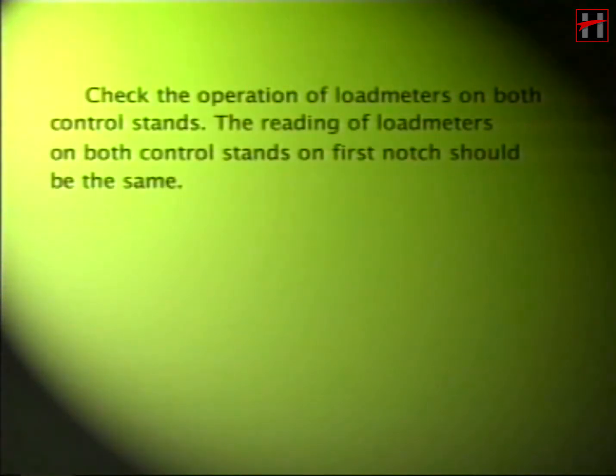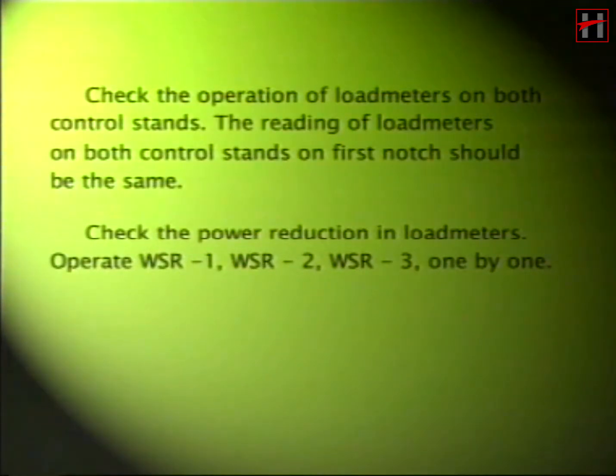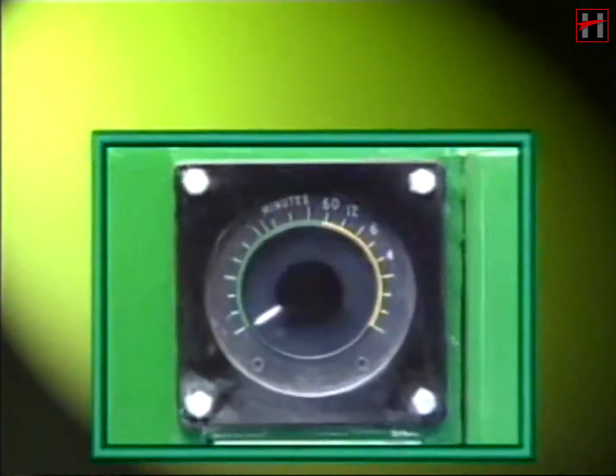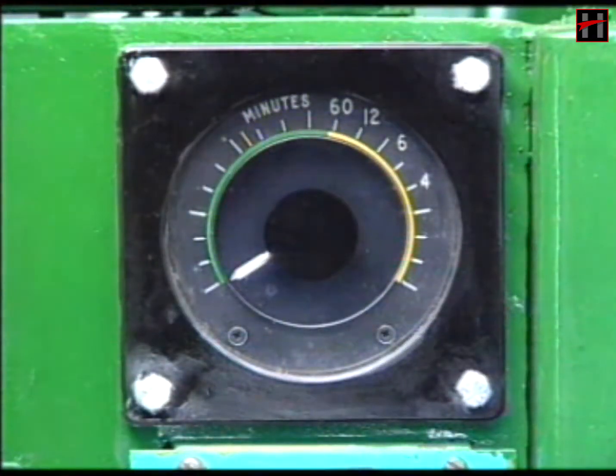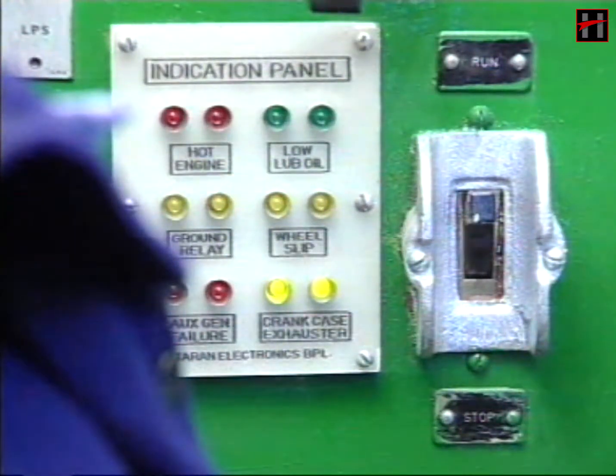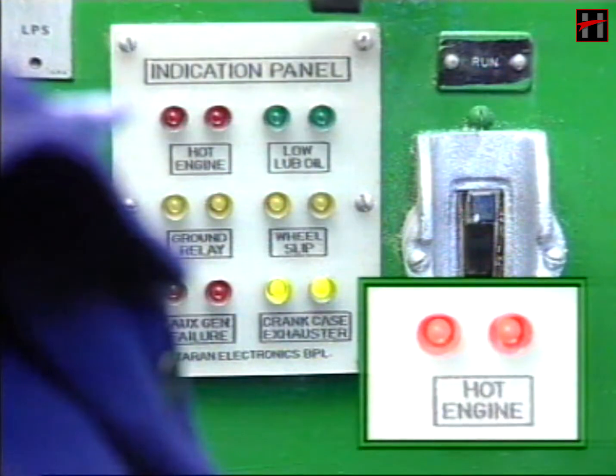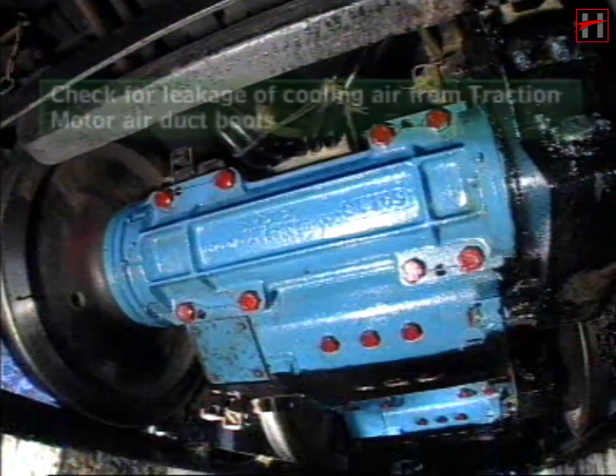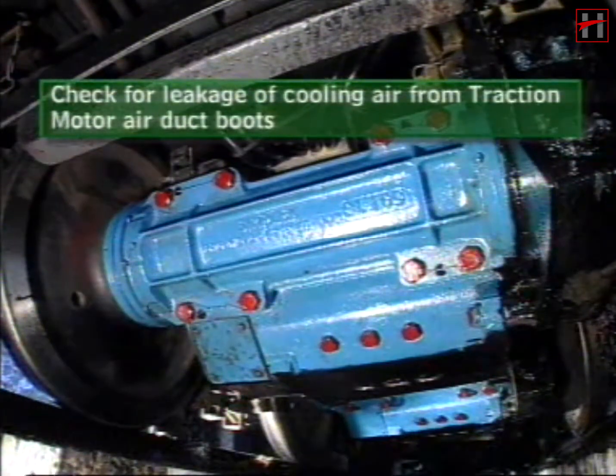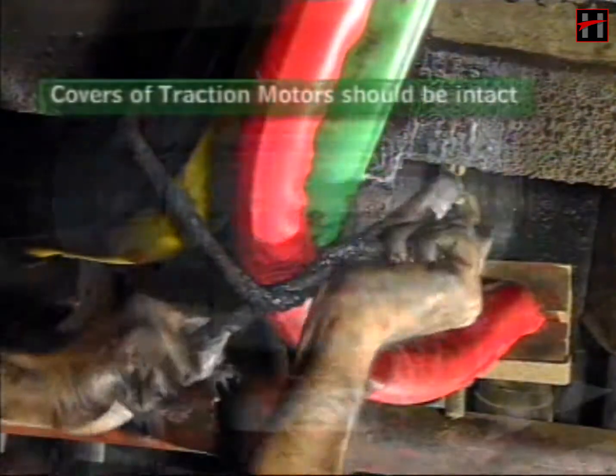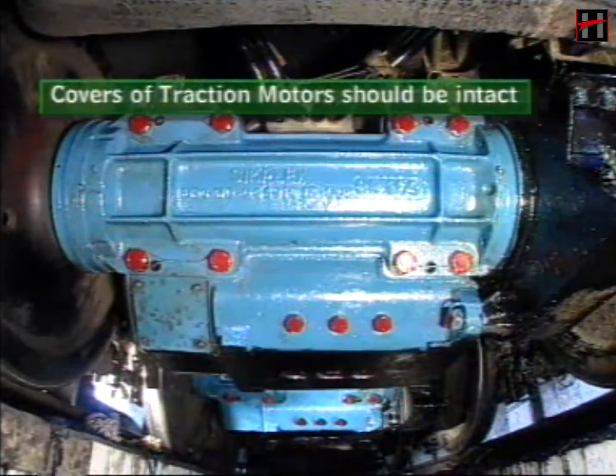Check the operation of load meters on both control stands. The reading of the load meters on both control stands on the first notch should be the same. Check the power reduction in load meter by operating the wheel slip relay 1, 2 and 3, turn by turn. The load meter needle should approach 0 on operation of the wheel slip relay. Check the indication lights on the indication panel. The indication lights should glow off and glow on for their respective items. Check for leakage of cooling air from the traction motor air duct boots. All the leads should be secured within cleats, and the covers of the traction motor should be intact.